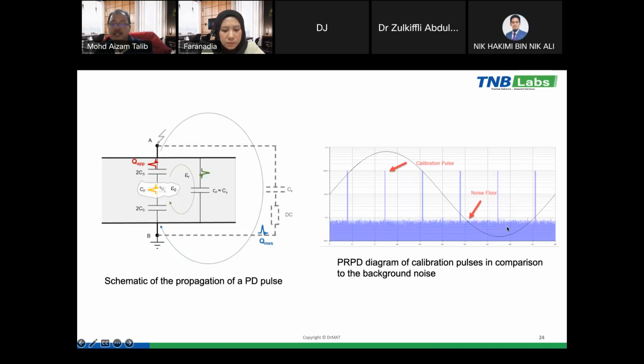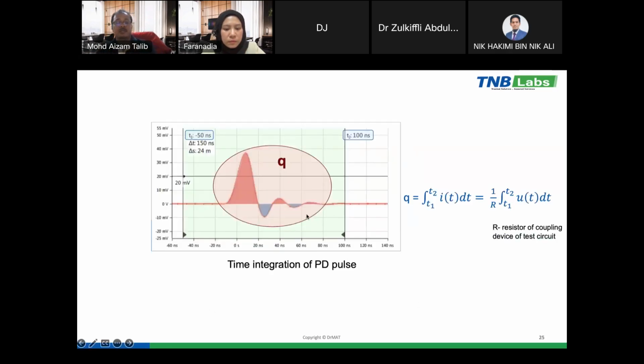And then this is the noise floor. Normally we need to eliminate the noise floor through a filtration system, or when we test in a Faraday cage, normally the noise floor is very small. And then what we do is integrate the energy inside this pulse. The integration of the PD pulse will give the apparent charge in units of picocoulombs.